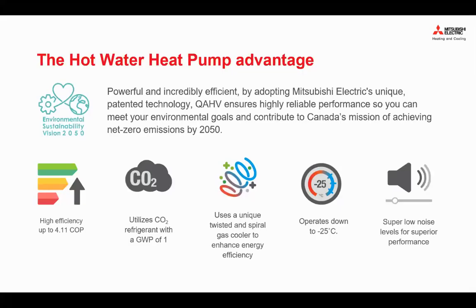Some of the key advantages of using the Mitsubishi hot water heat pump system: it is powerful and incredibly efficient by adapting our unique Mitsubishi patented technology, so it has reliable performance. It can also help achieve Canada's mission of net zero emissions by 2050. It is highly efficient, with efficiency up to 4.11 COP, so 1 kilowatt of power input can generate up to 4 kilowatts of heating output. It utilizes CO2, which is R744 refrigerant, with a global warming potential of 1, and it is also a natural refrigerant that we can source.